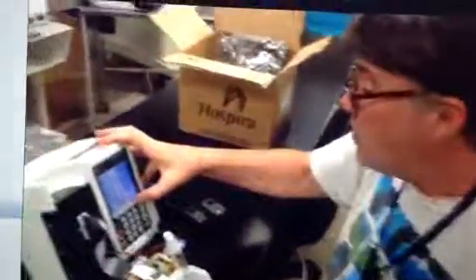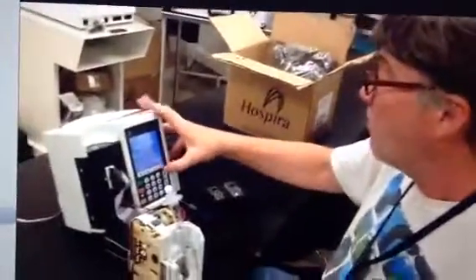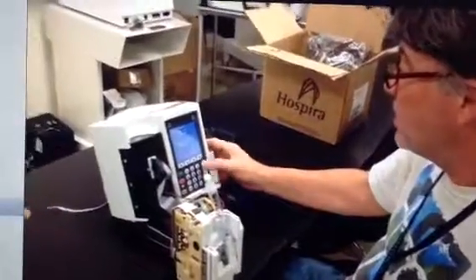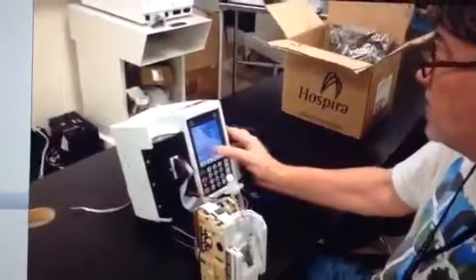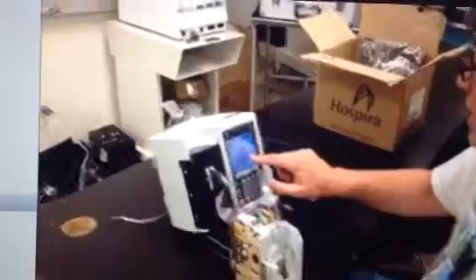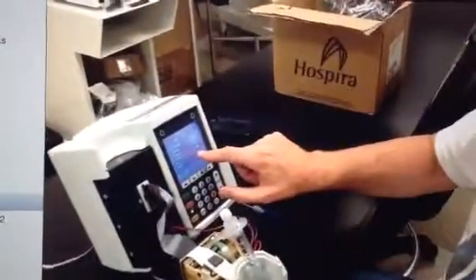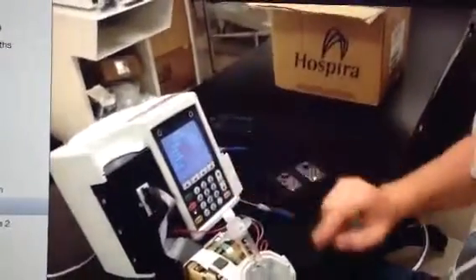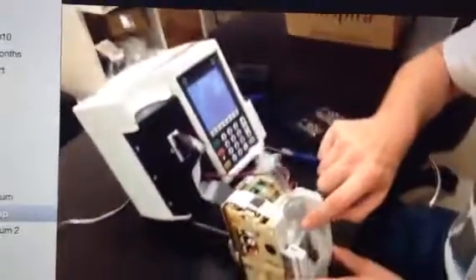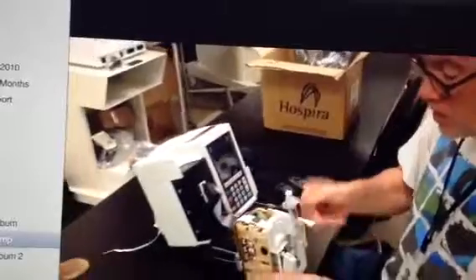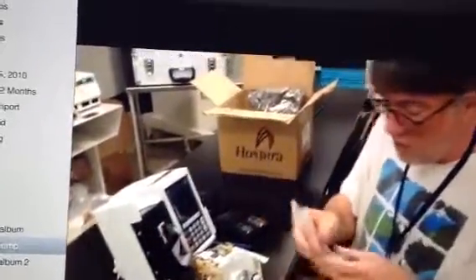If we had, we would hit back and hit 6 to verify. But here we see air does not show as done because we were not able to calibrate it with this cassette. We unplug this. I'm going to put a little more fluid in this and see if we can overcome that problem.